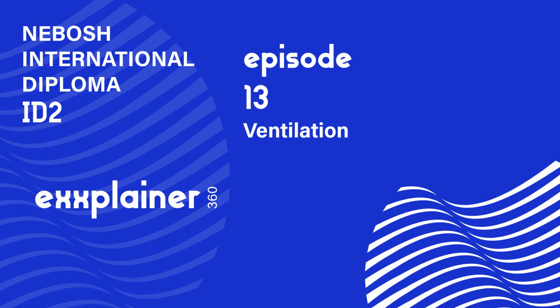What you're looking for is consistency. If the velocity varies by more than, say, 20% across the face, the flow is uneven, and the capture won't be effective across the whole opening. Okay, face velocity. What's the second measurement?